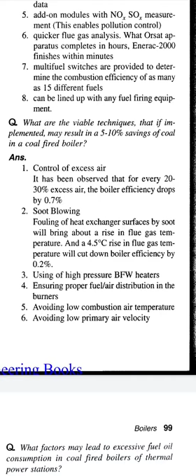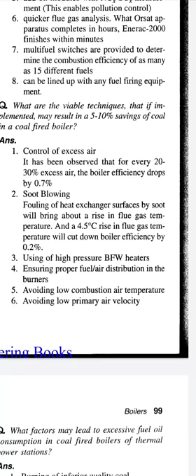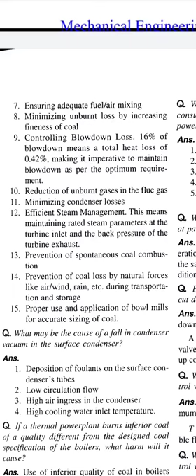Using of high pressure boiler feed water heaters. Ensuring proper fuel air distribution in the burners. Avoiding low combustion air temperature. Avoiding low primary air velocity. Ensuring adequate fuel air mixing, minimizing unburnt loss by increasing fineness of coal, controlling blowdown loss. 16% of blowdown means a total heat loss of 0.42%, making it imperative to maintain blowdown as per the optimum requirement. Reduction of unburned gases in the flue gas, minimizing condenser losses.